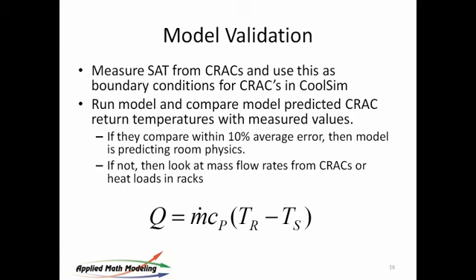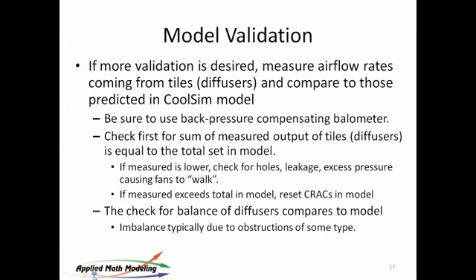And what's going on under the floor. They can also be walking a fan curve too. That's exactly right. So if the delta P is too high, if there's too much resistance under the floor, if the subfloor is 8 inches or 6 inches, or there's 30–40% or more of the cross-sectional area blocked, then it's likely that the fan will not be producing what the spec is, because it's got too much pressure drop across it. So that's something to look for.